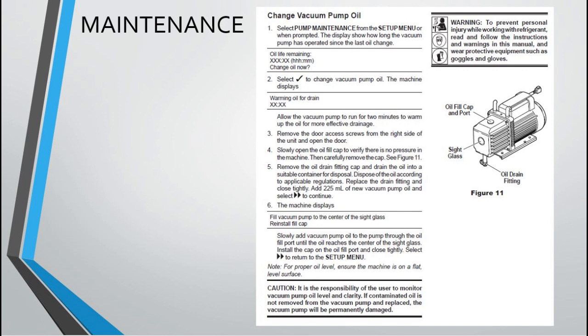Slowly open the oil fill cap to verify there is no pressure in the machine. Then carefully remove the cap. See Figure 11. Remove the oil drain fitting cap and drain the oil into a suitable container for disposal. Dispose of the oil according to applicable regulations. Replace the drain fitting and close tightly. Add 225 milliliters of new vacuum pump oil and select to continue.